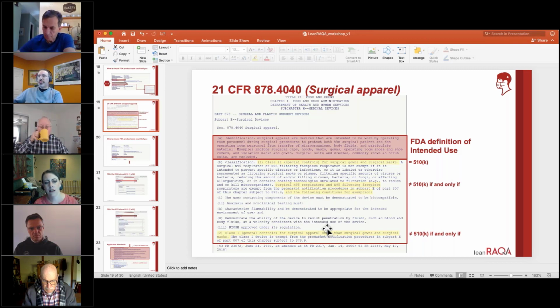They're filing underneath this MSH product code, and they're brand new, and there's no way they have had time to do full biocompatibility testing, to fully characterize flammability, to fully do their fluid resistance testing, and to get US NIOSH certified. So people who have brand new registrations and listings under MSH have misinterpreted this regulation and are misbranding their product.